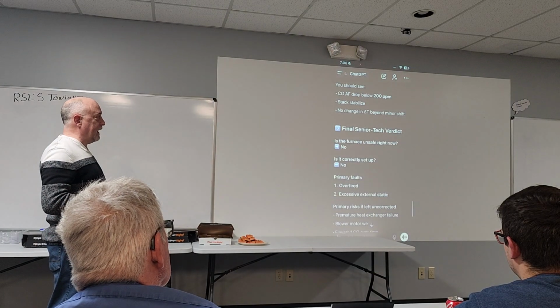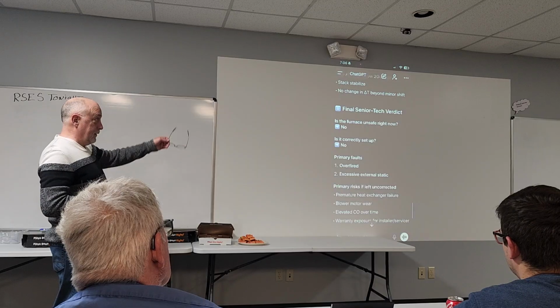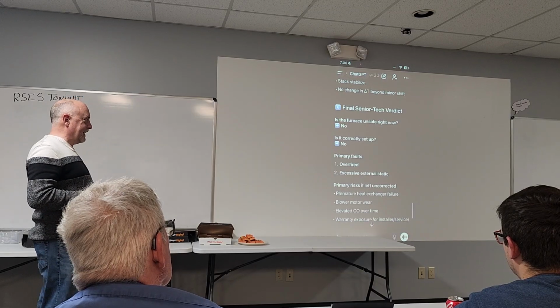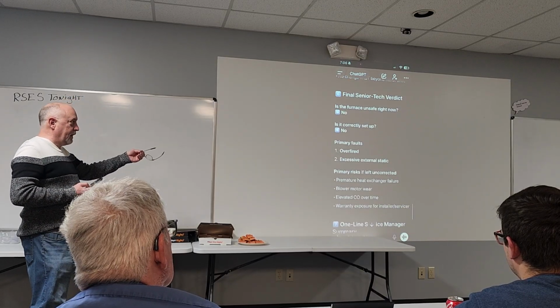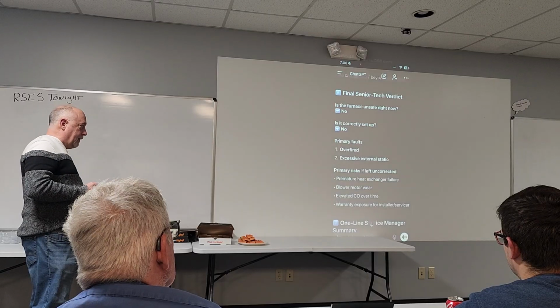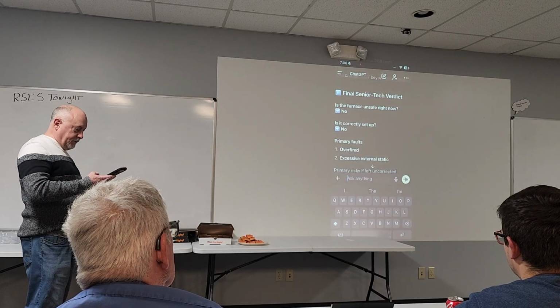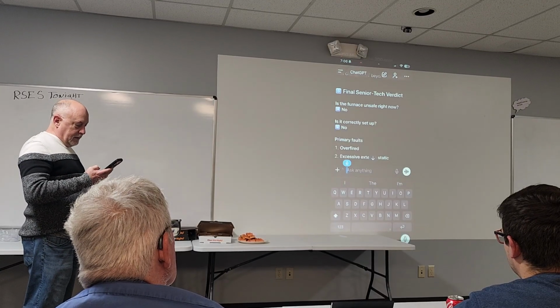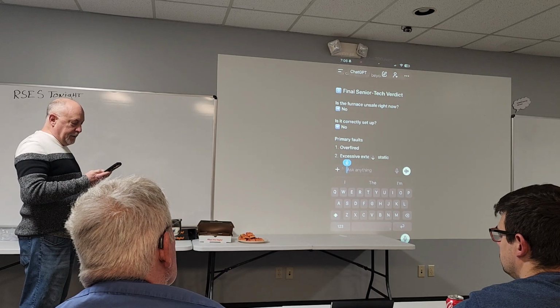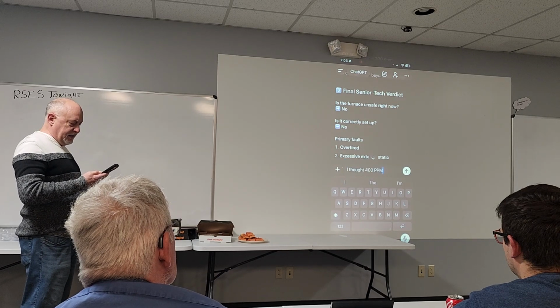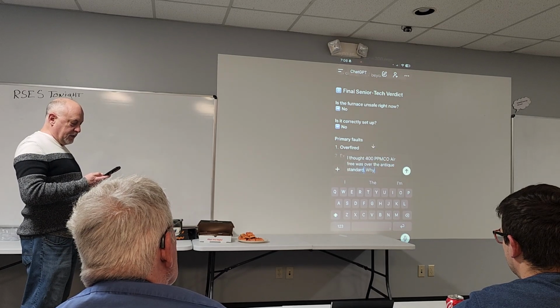Is the furnace unsafe now? Yes. No, apparently not. Is it set up correctly? No. Primary result: overfire. So, yeah, let's give it a correction. I thought 400 ppm CO air free was over the ANSI standard. Why the hell are you telling me that's okay?